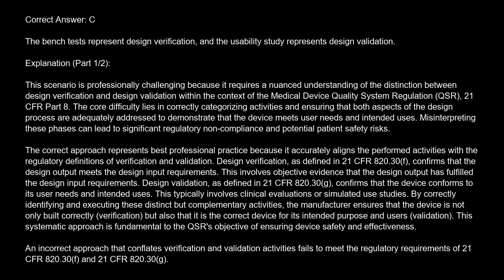Misinterpreting these phases can lead to significant regulatory noncompliance and potential patient safety risks. The correct approach represents best professional practice because it accurately aligns the performed activities with the regulatory definitions of verification and validation. Design verification, as defined in 21 CFR 820.30(f), confirms that the design output meets the design input requirements.